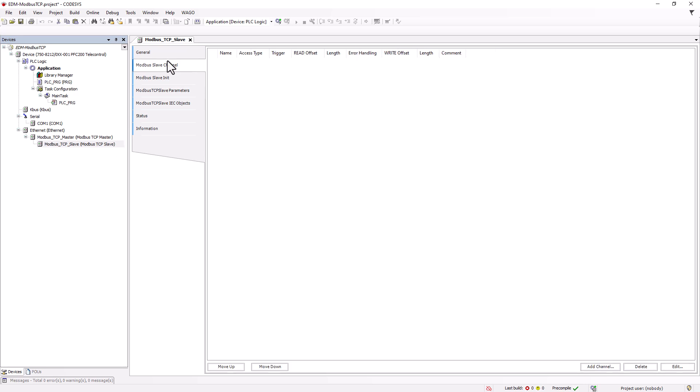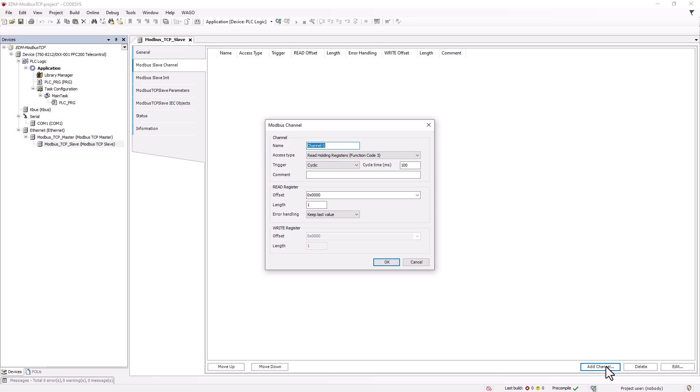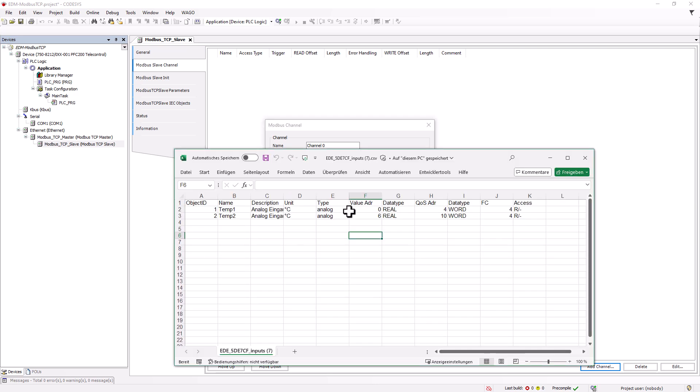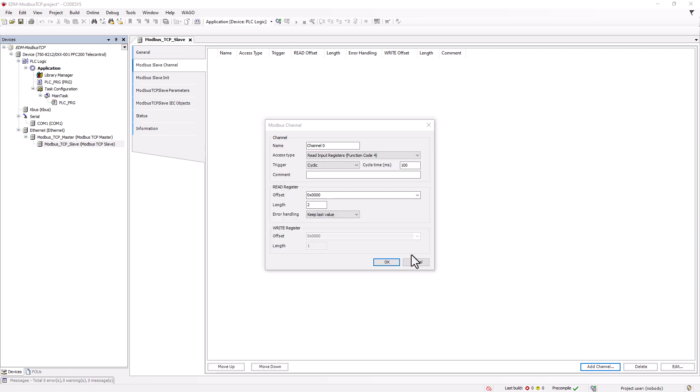Then we create two Modbus channels, with function code 4, read input registers. The channel length is 2, because the EDM returns the readings in two words. The channel offset, that is the start address, can be found in the previously exported CSV file.